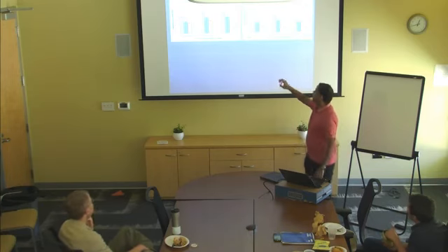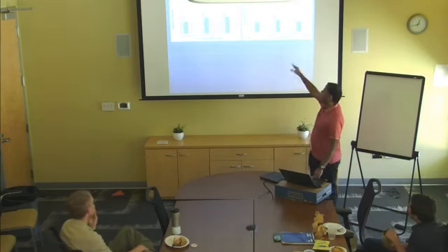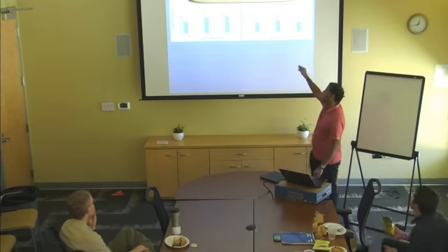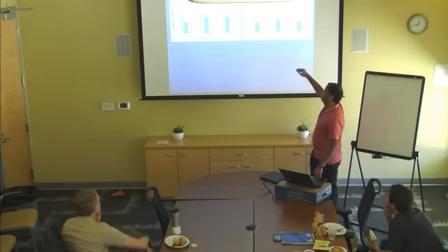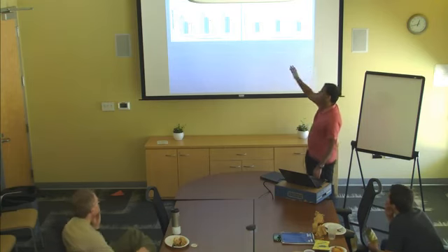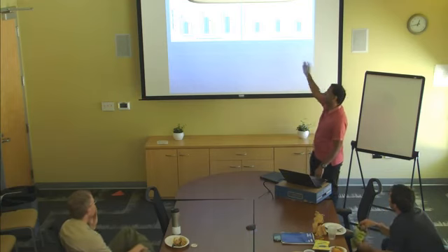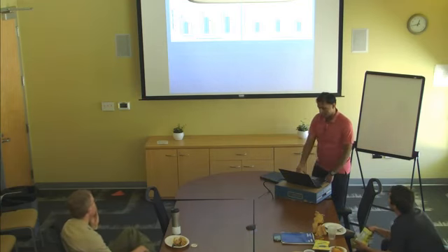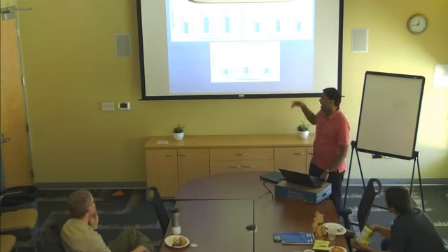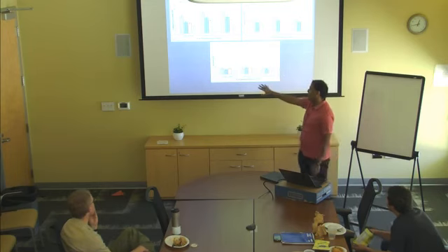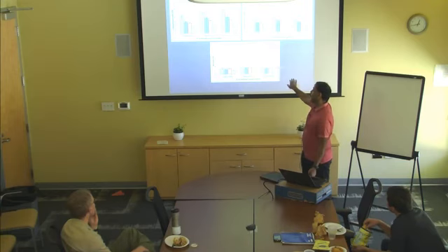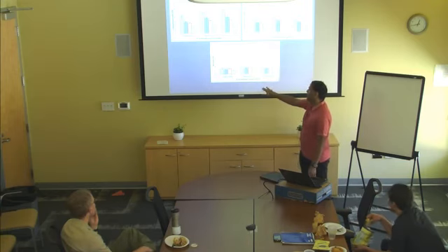But as we go to the equipment COP, which now includes the fan power and fan heat, the values come down, and it kind of negates some of the advantages of the thermodynamic efficiency. And finally, when you include the heat transfer impacts of the distribution system and look at the system COP, you can see that the points are basically flat, like the system COP is almost insensitive to changes in airflow rate.